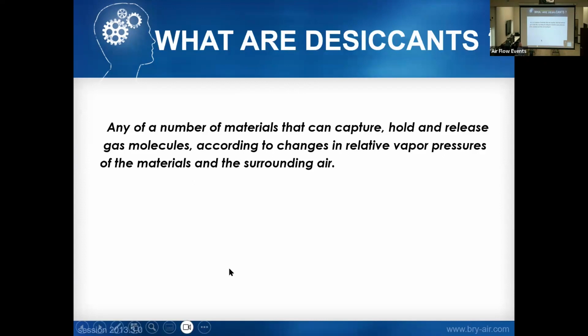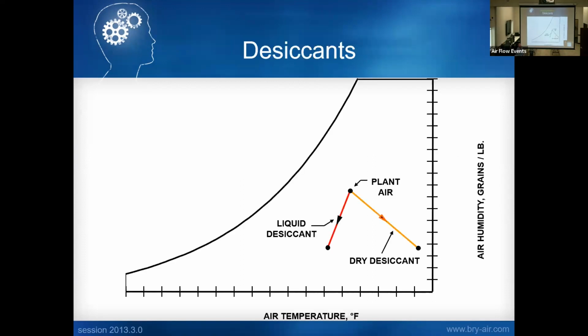So a little bit about what we're talking about. Desiccants are materials that can capture the moisture and release it, the molecules. That's kind of the principle behind dehumidification. You've kind of seen this slide already. Basically, a liquid desiccant is going to remove moisture and cool down the air. The dry desiccant, which is what we use, basically just look at the desiccant rotor itself. Due to the reactivation, the regeneration, the air gets heated up as it removes the moisture.